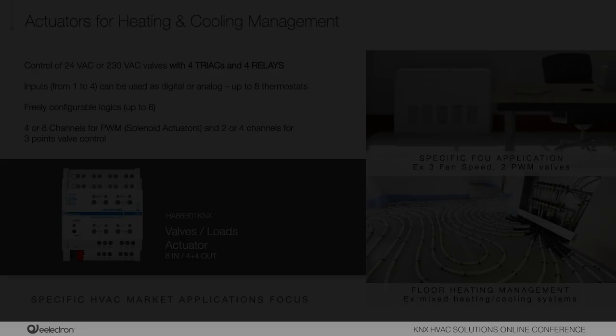To complete the HVAC range, Eelectron also offers an actuator with 4 relays and 4 TRIACs, sharing the same functions as the heating actuator but covering additional HVAC applications — for example, a four-pipe fan coil with on/off speed and valve managed by TRIACs. Free relays can control lighting circuits. TRIACs are recommended for valve control to reduce noise in apartments and improve occupant comfort.